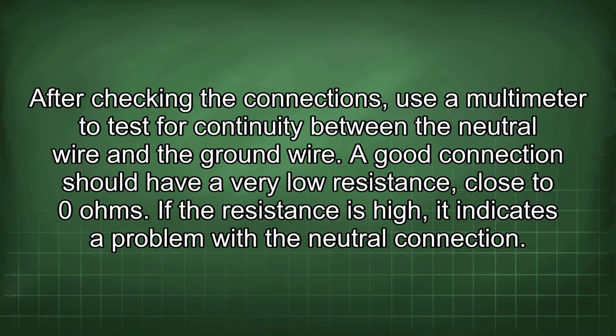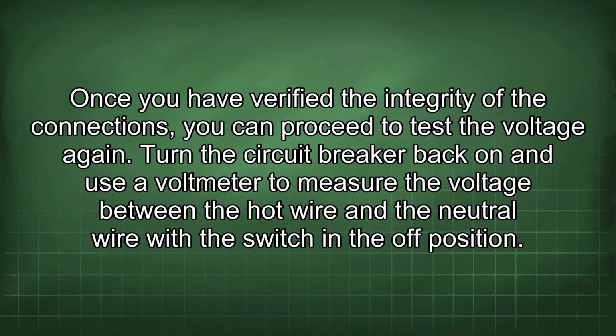After checking the connections, use a multimeter to test for continuity between the neutral wire and the ground wire. A good connection should have a very low resistance, close to 0 ohms. If the resistance is high, it indicates a problem with the neutral connection. Once you have verified the integrity of the connections, you can proceed to test the voltage again.